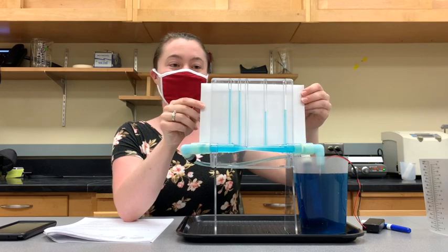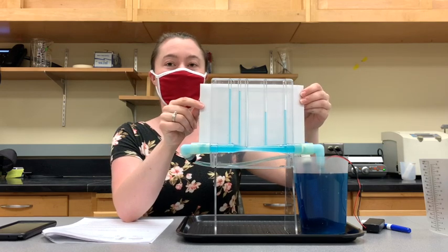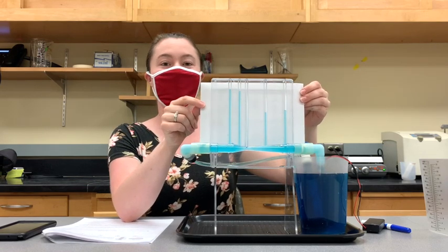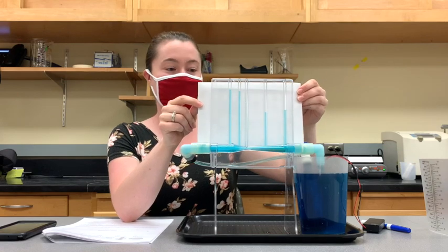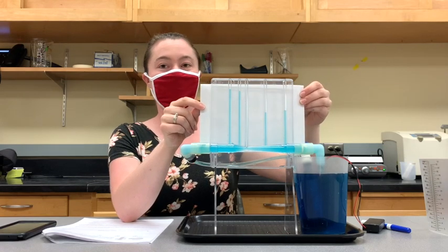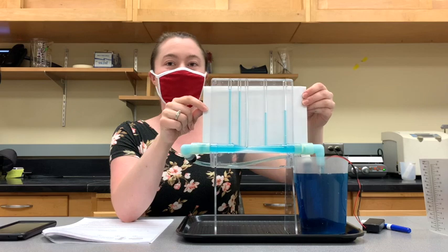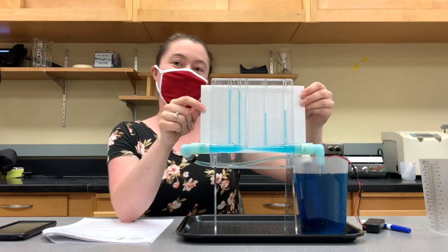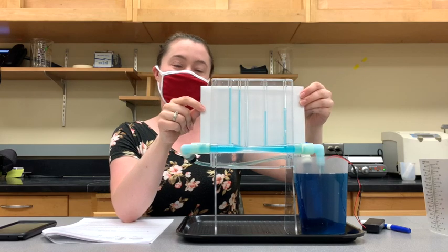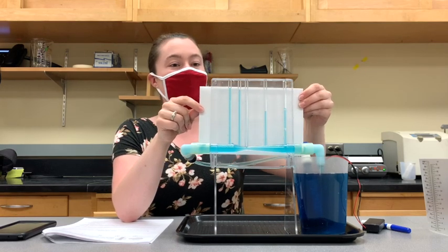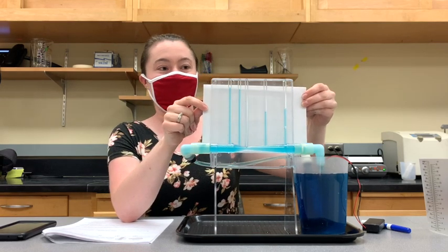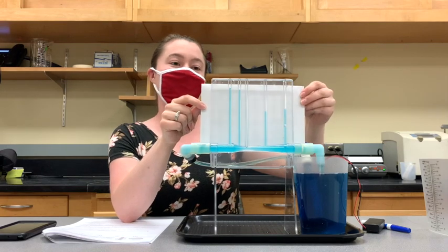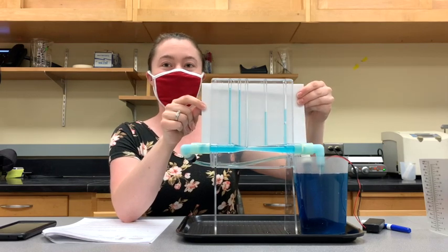at the inlet of the Venturi when our diameter of the pipe is large, and as the diameter decreases towards the throat, we see a non-linear decrease in the pressure. Our pressure is lowest at the throat of the Venturi when we have the smallest diameter, and then as the diameter expands to the exit of the Venturi, our pressure goes back up. You can also see that the pressure doesn't recover completely by the exit of the Venturi, and that's actually because of frictional losses in the pipe.